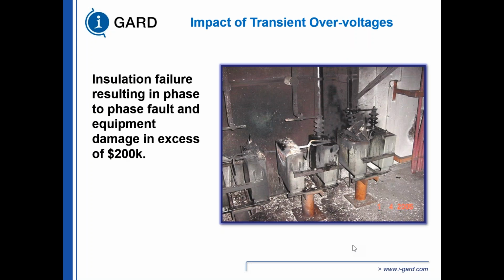Here is more damage that's associated with intermittent arcing faults. And you can see that there's very destructive overvoltages that occur and just totally destroy your system. Damage in this particular facility, I believe it was 15 kV, is in excess of $200,000. This wasn't due to a ground fault. This was due to an intermittent ground fault, which went undetected on an ungrounded system. And unfortunately, the overvoltages collapsed the entire system.